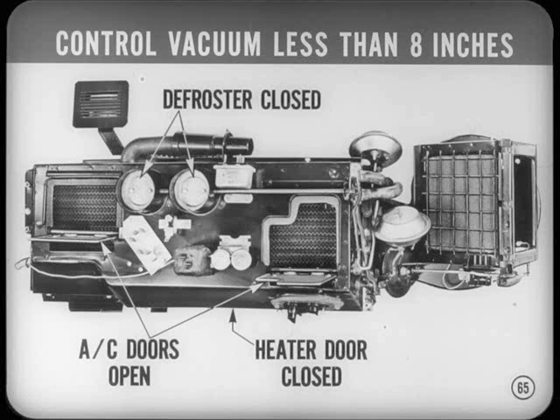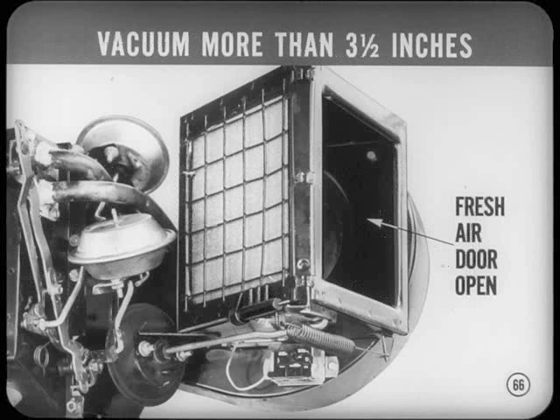And what about the fresh air door? The fresh air door stays all the way open whenever control vacuum is more than about 3½ inches. At very low control vacuum, the system is calling for maximum cooling, so the system reduces fresh air intake to about 20%. You better tell Jack about that 20% fresh air switch, Bob.